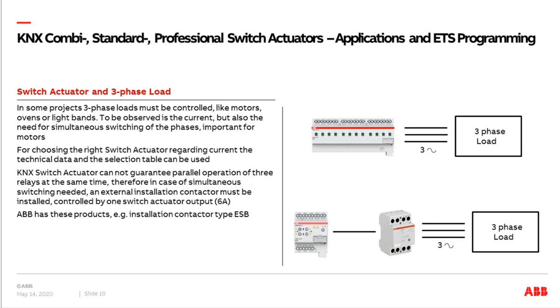If you want to solve it for sure and don't want to take any risk, of course you take any installation contactor in between. Again, our switch actuator only operates as a control circuit, and then a real three-phase contactor guarantees parallel simultaneous operation of three outputs, and then you connect your three-phase load. This is also relevant when you have high currents needed that cannot be handled with our relays, in which case you also have to take such a contactor behind.